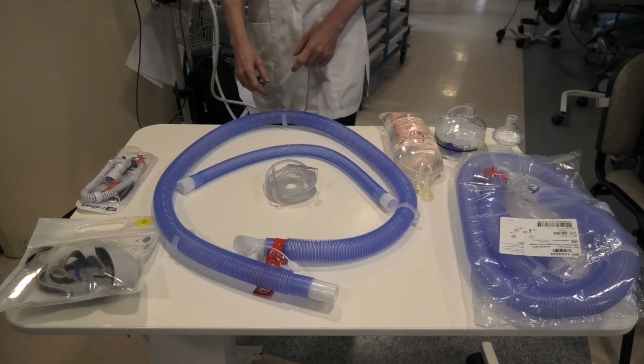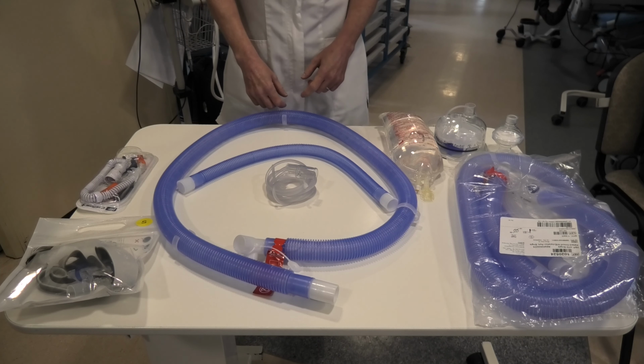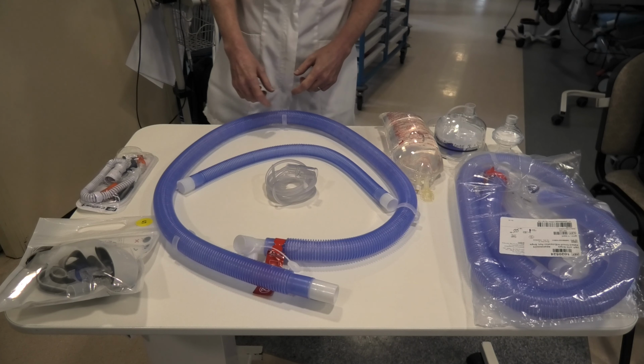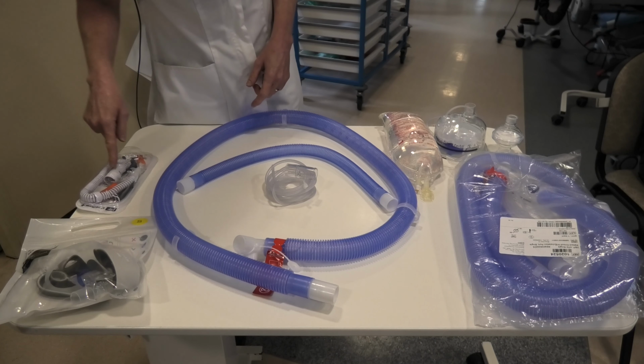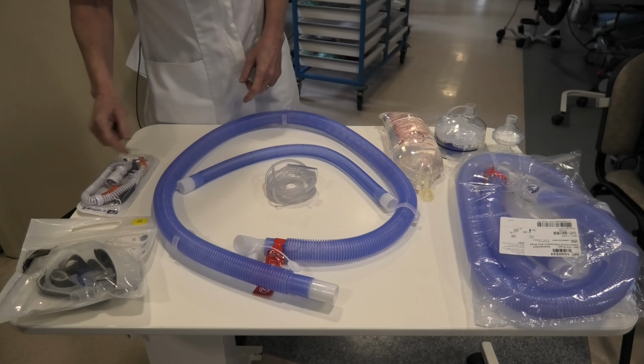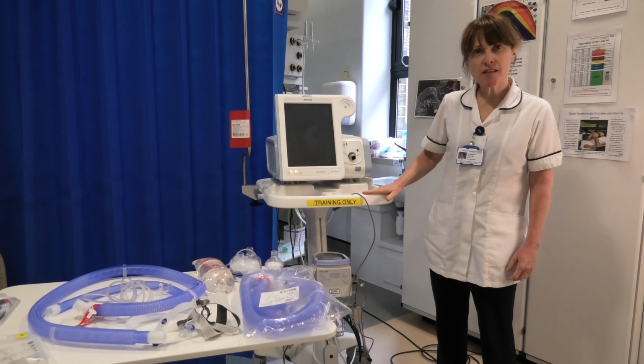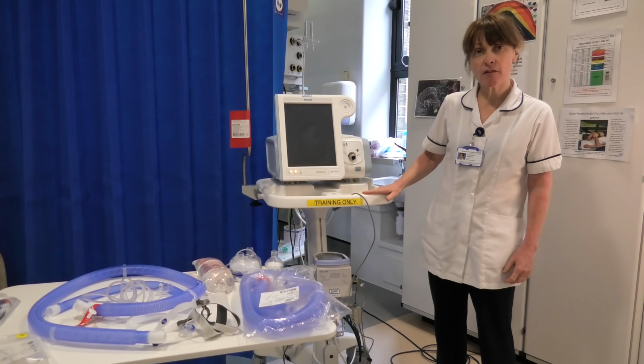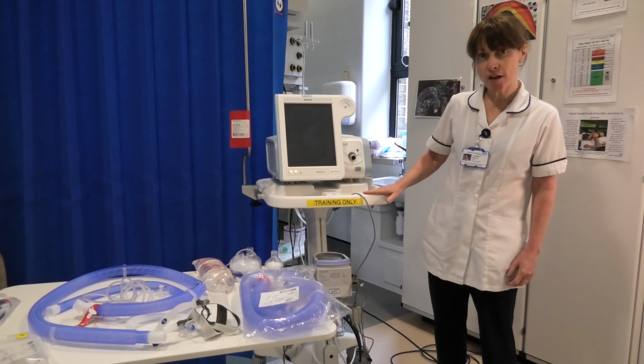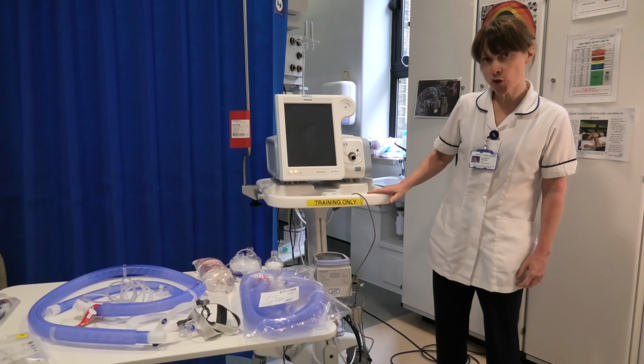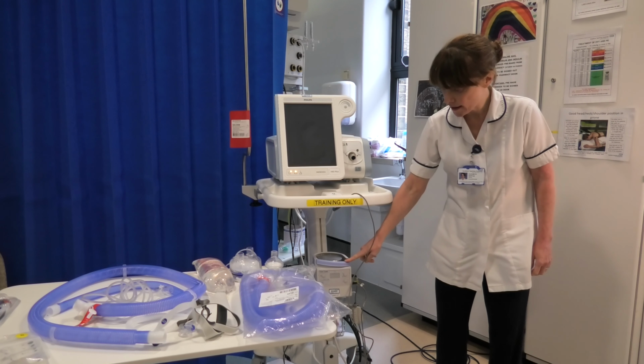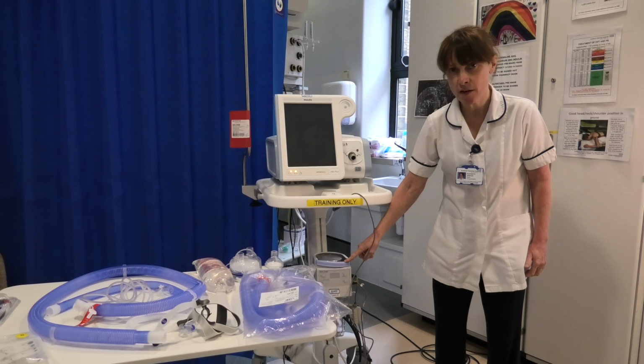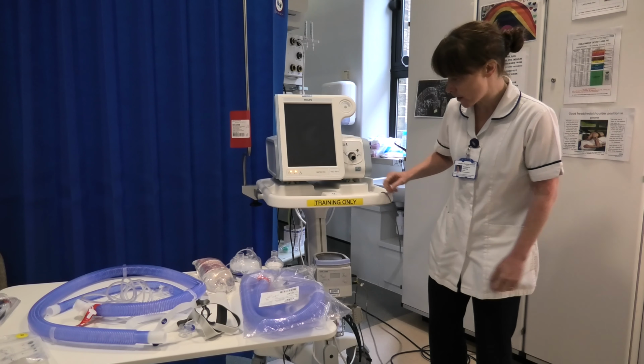If you're using CPAP, you would use a face mask, a non-invasive ventilation face mask. If you're using nasal high flow, you would use a specialist nasal cannula. So I'm going to show you how to set up the V60 using it as a nasal high flow or a CPAP with a wet circuit. So we'll set up the wet circuit first using a Fisher-Paykel humidifier, which is called an F&P 850.